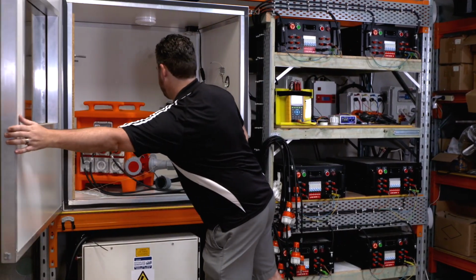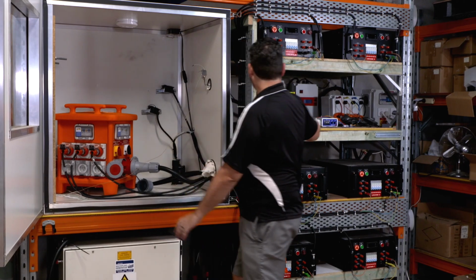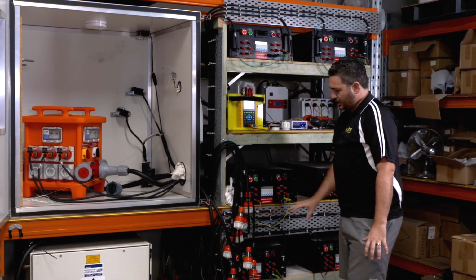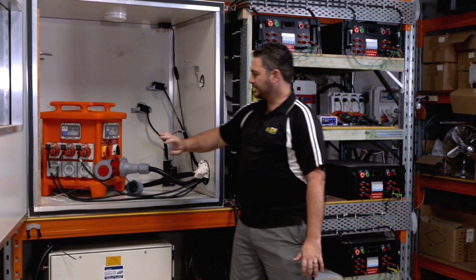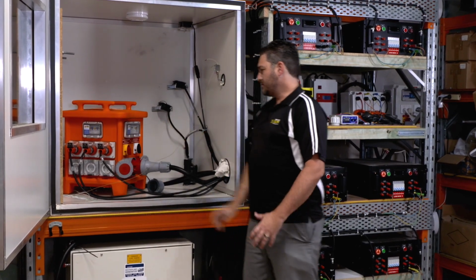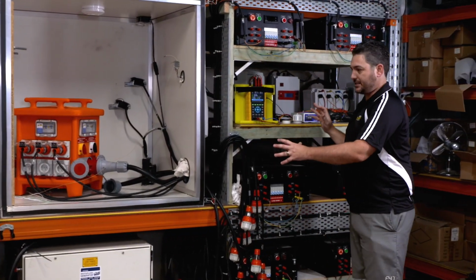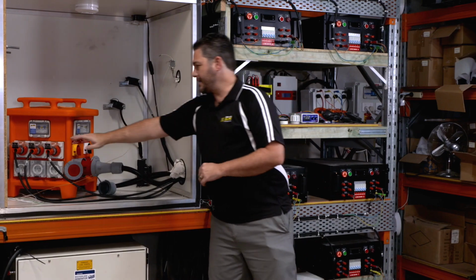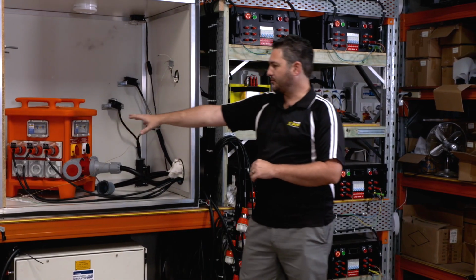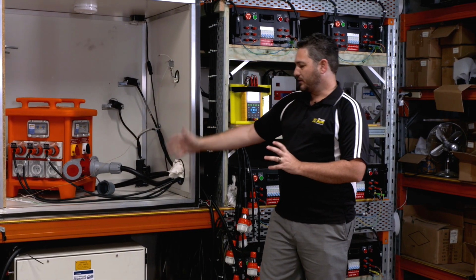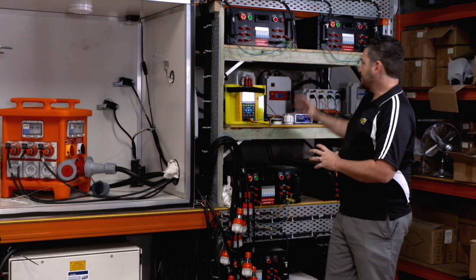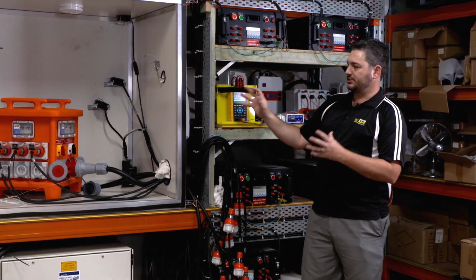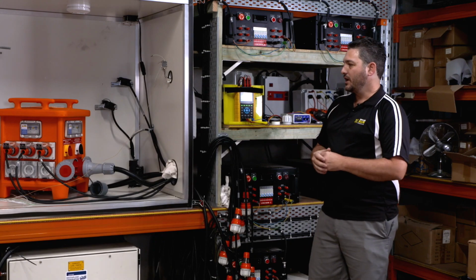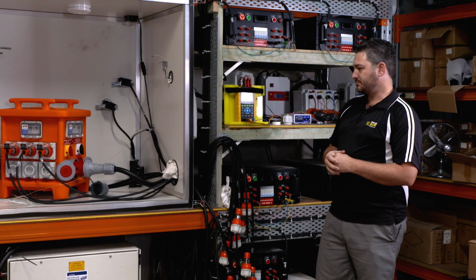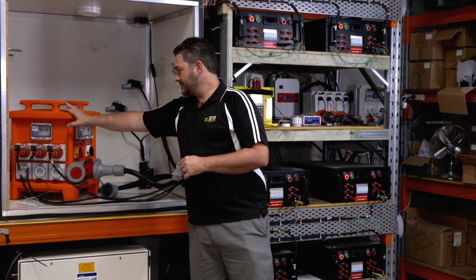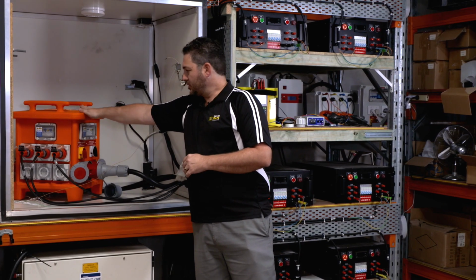What we do then is we've got load banks, all different single phase load banks, some 3-phase load banks, all plugged into the board. And what we do then is we turn these on, we get them all cranked up to pull the full load amps out of the board. So what we've got here is a 63 amp board. So we crank up the 3-phase, we get the single phase going to pull that whole 63 amps out of the board and monitor those internal temperatures. On this board here, with no thermal management, you won't be able to do that.